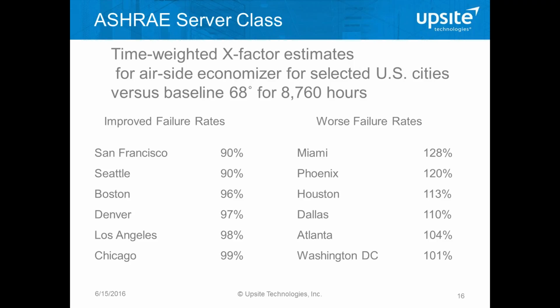So you can see we've got some cities that were going to have lower failure rates of our servers if we ran the data center without any air conditioning. And then we have some cities where we have higher failure rates. But we just want to put that a little bit into perspective, and we can use Phoenix as an example for that, where if we ran a data center in Phoenix with A3 servers and we had no air conditioning, we would see a 20% increase in server failures. But let's say, for example, our true experience has been that we see maybe only 3 servers die on us in a year. So a 20% increase would actually only be 0.6. So it would take us 2 years to actually see an additional failure.